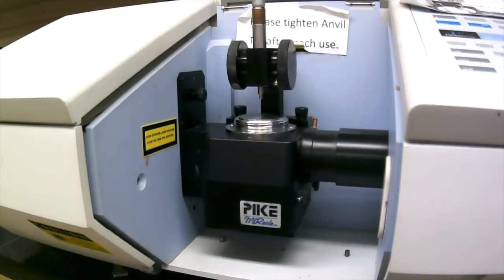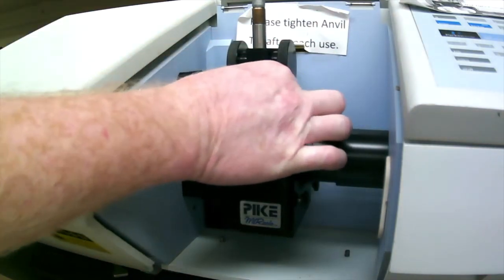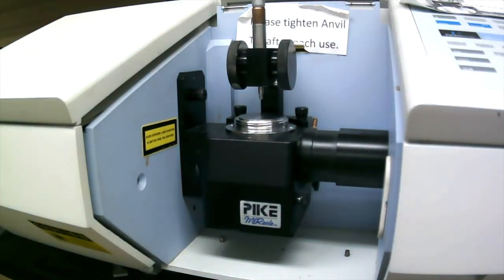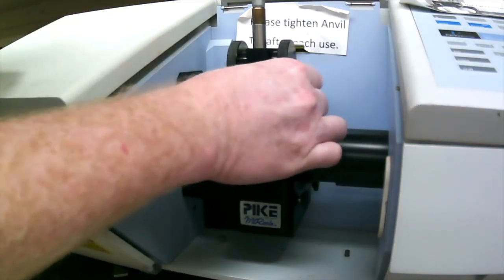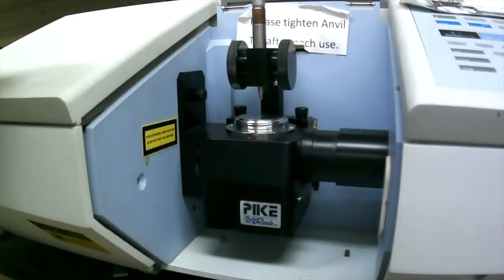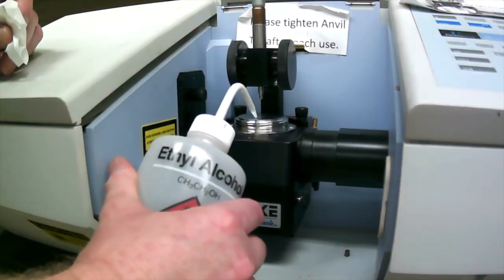All right, so now when I'm done running a scan, I want to clean the sample off. If it's a liquid, what you want to do is take a chem wipe and mop up most of the liquid. Got it. Maybe use a couple. And then after you've done that, then you want to clean the ATR adapter with some ethanol. That's our cleaning solvent.